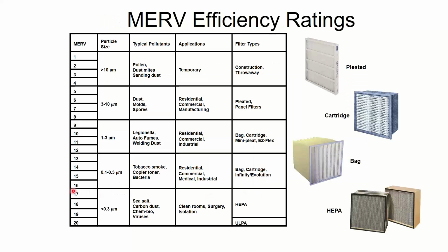This chart kind of explains that. The MERV rating scale goes from 1 to 16. Some people will incorrectly say it goes to 20 and say that 17 through 20 is for different versions of HEPA. Technically, HEPA filters are not covered under the current ASHRAE 52.2 MERV rating system, but conceptually, if they were, they would be the 17 to 20 range. But there's a separate testing standard just for HEPA. So for discussion purposes, we'll pretend that HEPA is 17 through 20, but officially just know that it stops at 16, and above that would be a different standard. So 1 through 16 is my MERV rating.